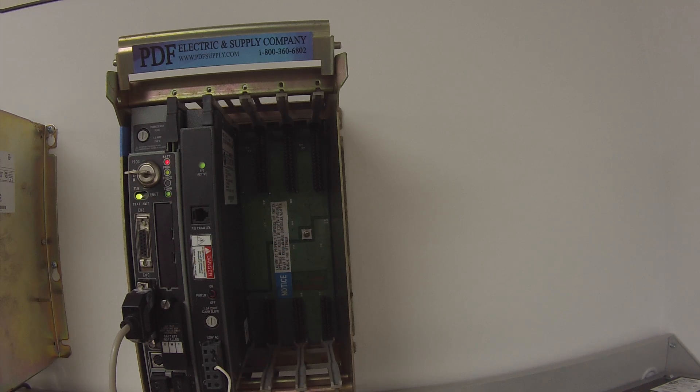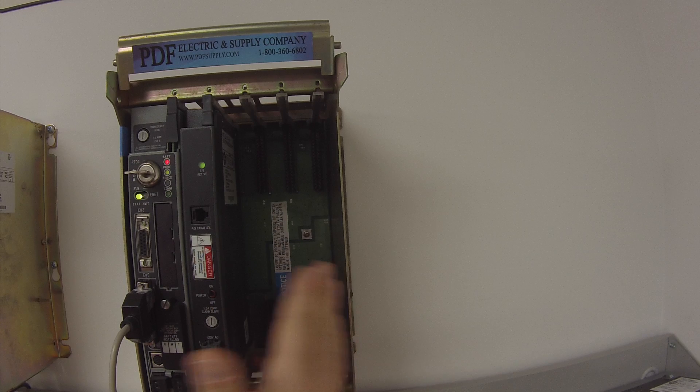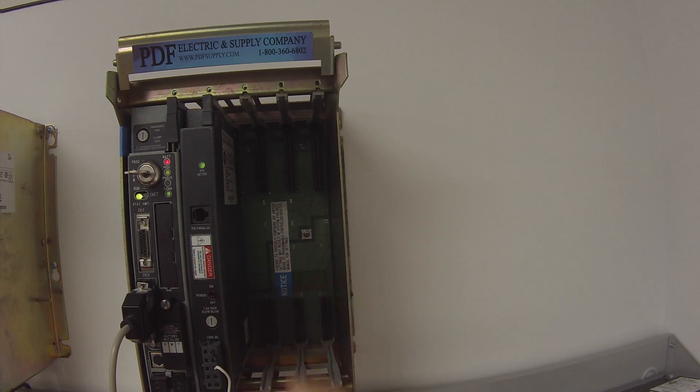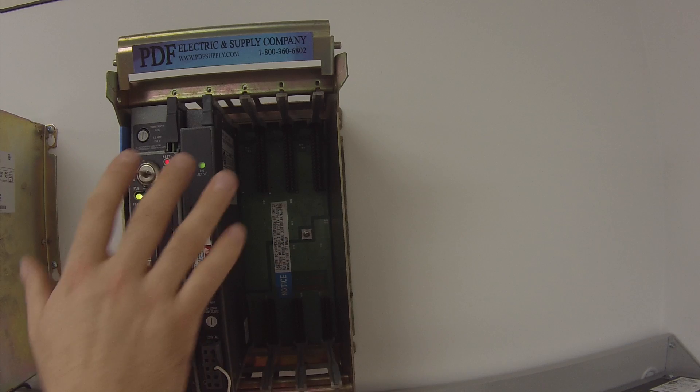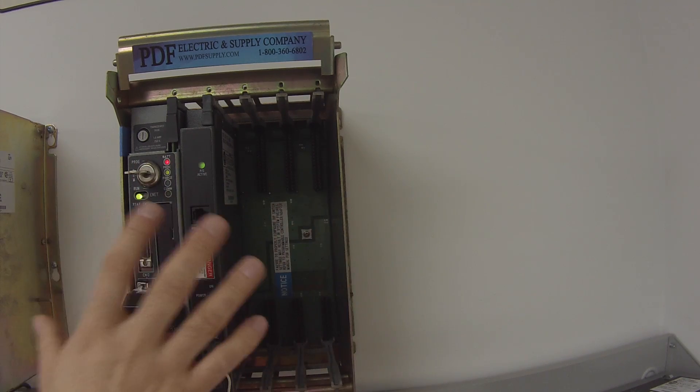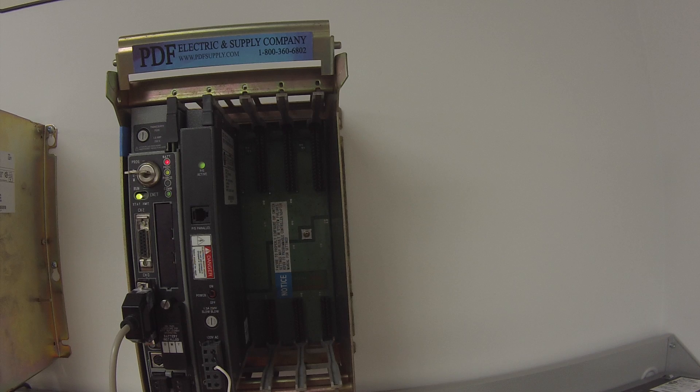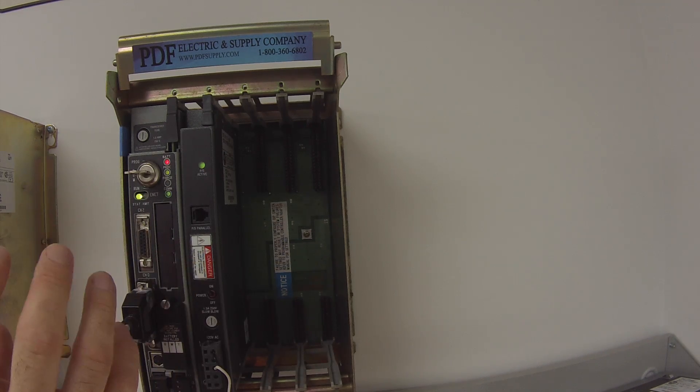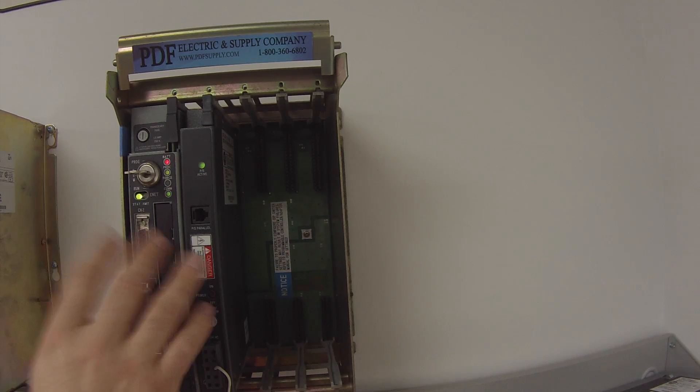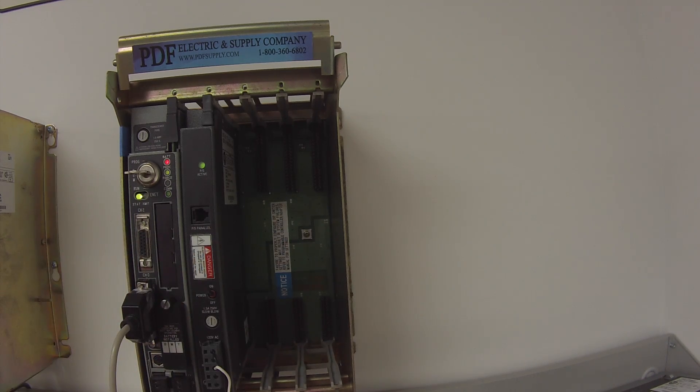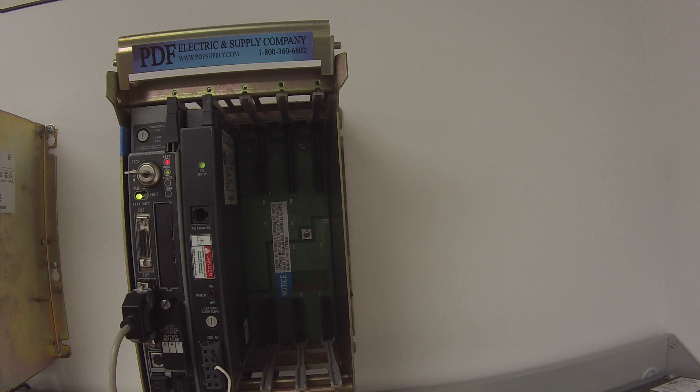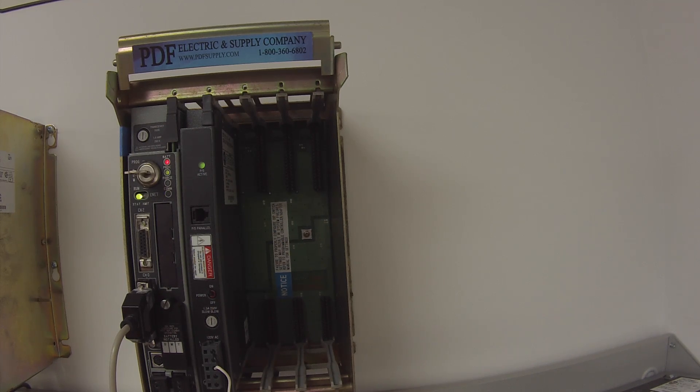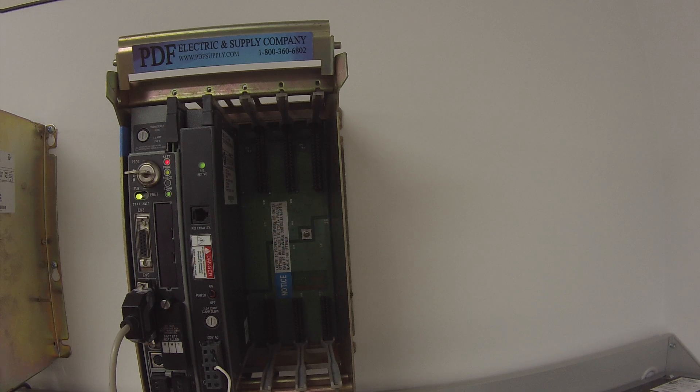The third part of the test would be perhaps to fill this with I.O. modules, maybe put plastic or cardboard on the bottom and the top of this chassis, and I do that because I want to increase the heat. Put the processor under more of a load, more of an actual factory situation, and leave it running for two or three days. We usually do it over a weekend, Friday, Saturday, Sunday. We come in on Monday, and we feel that if the processor's still running and there's no error codes and it's perfect, then it's a good, healthy processor.